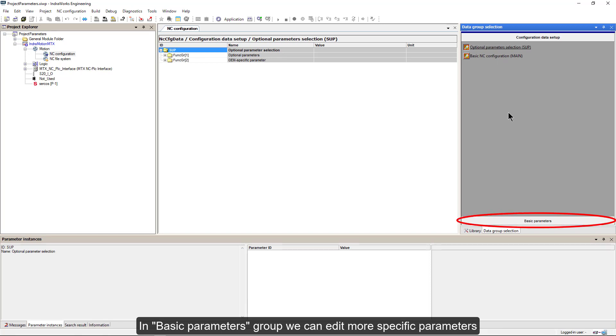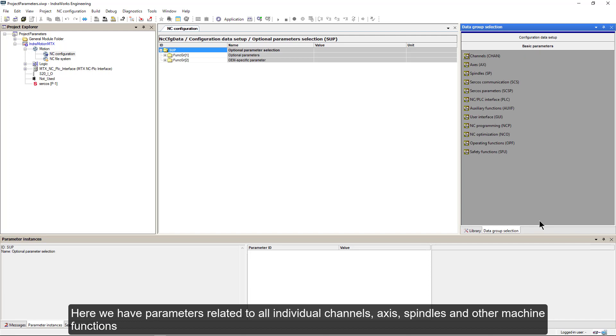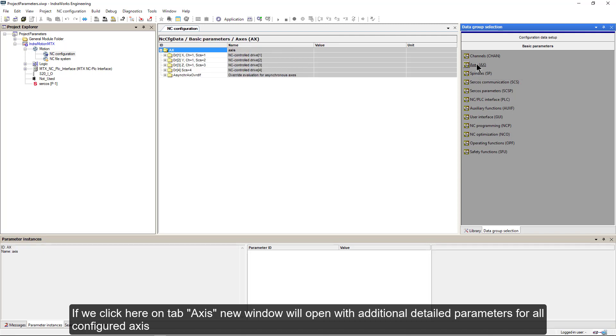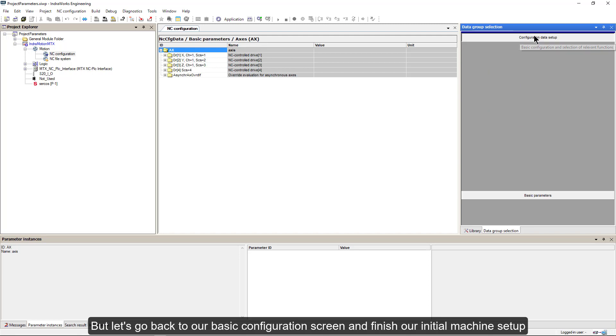In basic parameters group, we can edit more specific parameters. Here we have parameters related to all individual channels, axes, spindles and other machine functions. If we click here on tab Axis, new window will open with additional detailed parameters for all configured axes. But let's go back to our basic configuration screen and finish our initial machine setup.